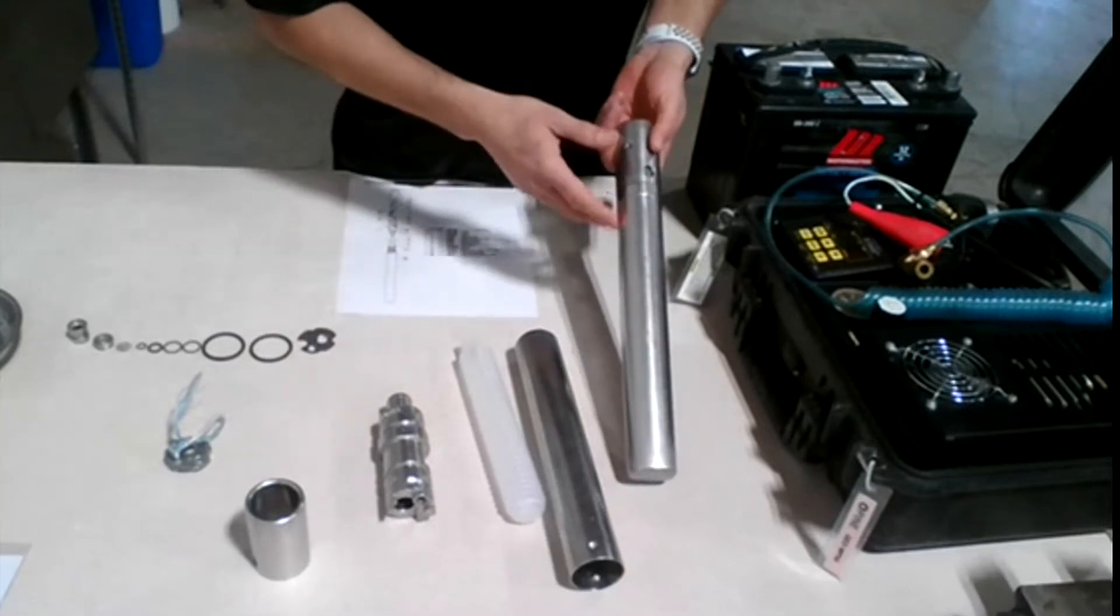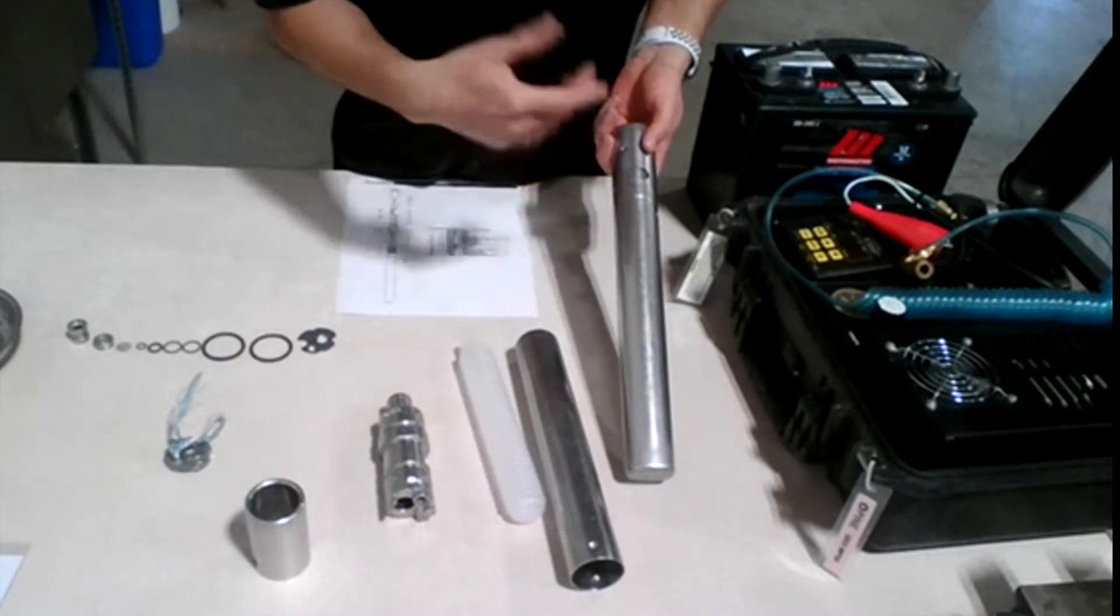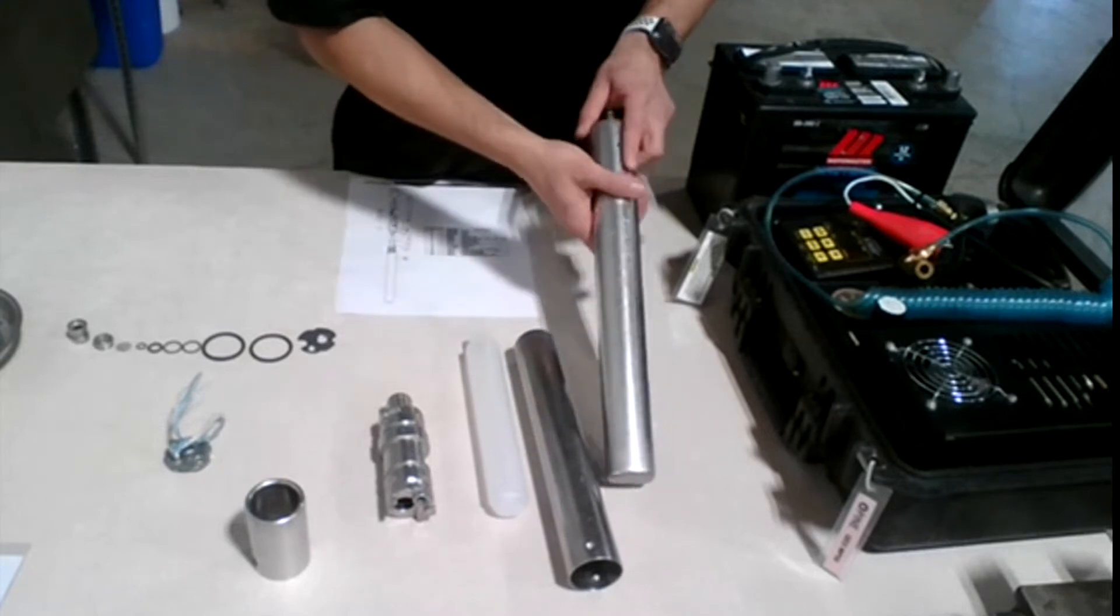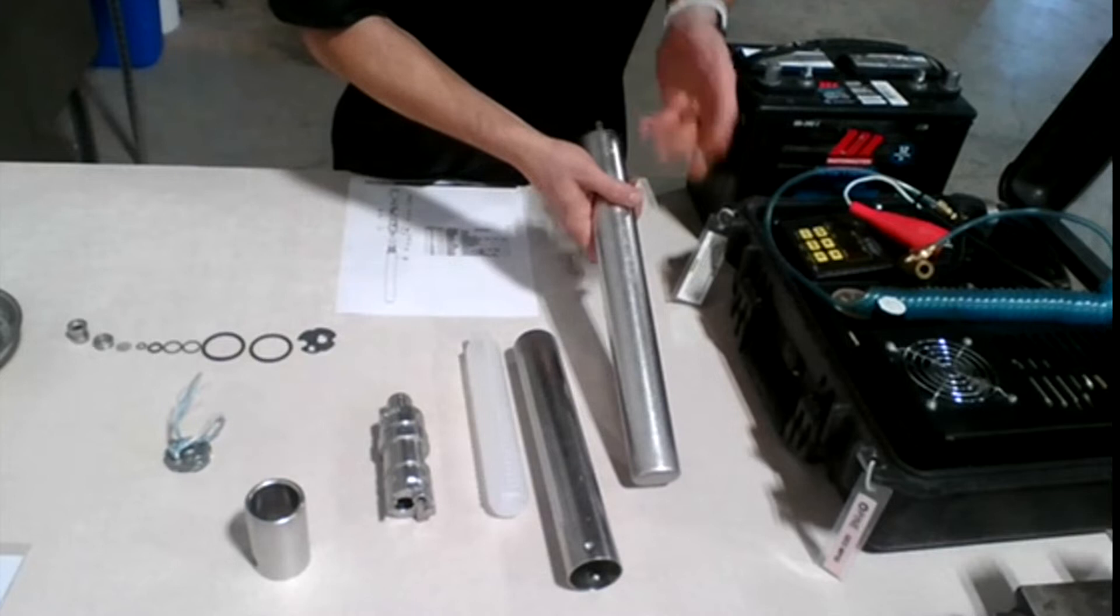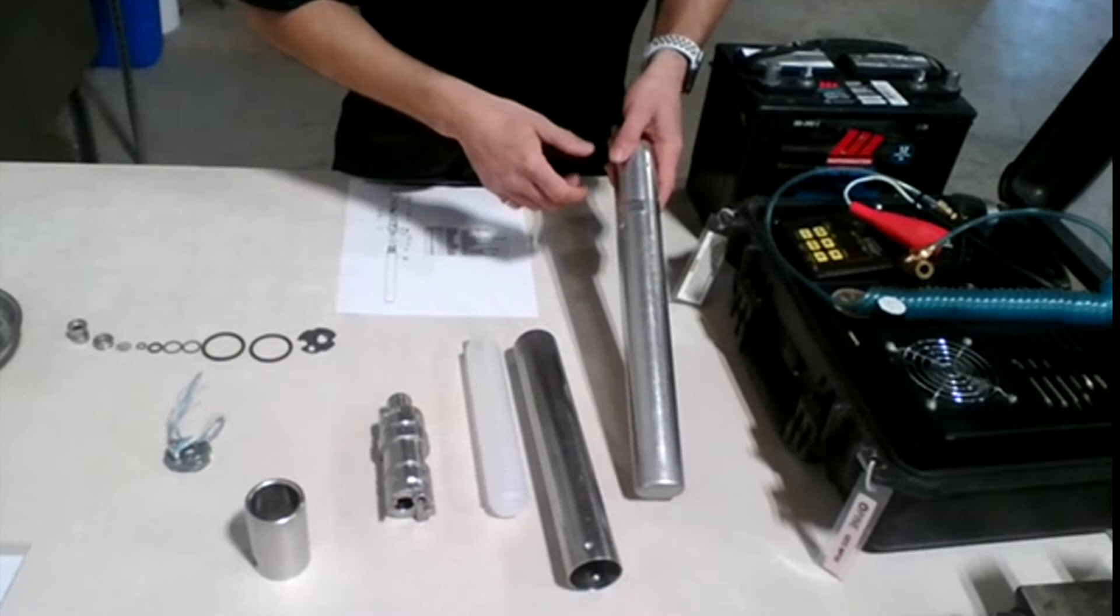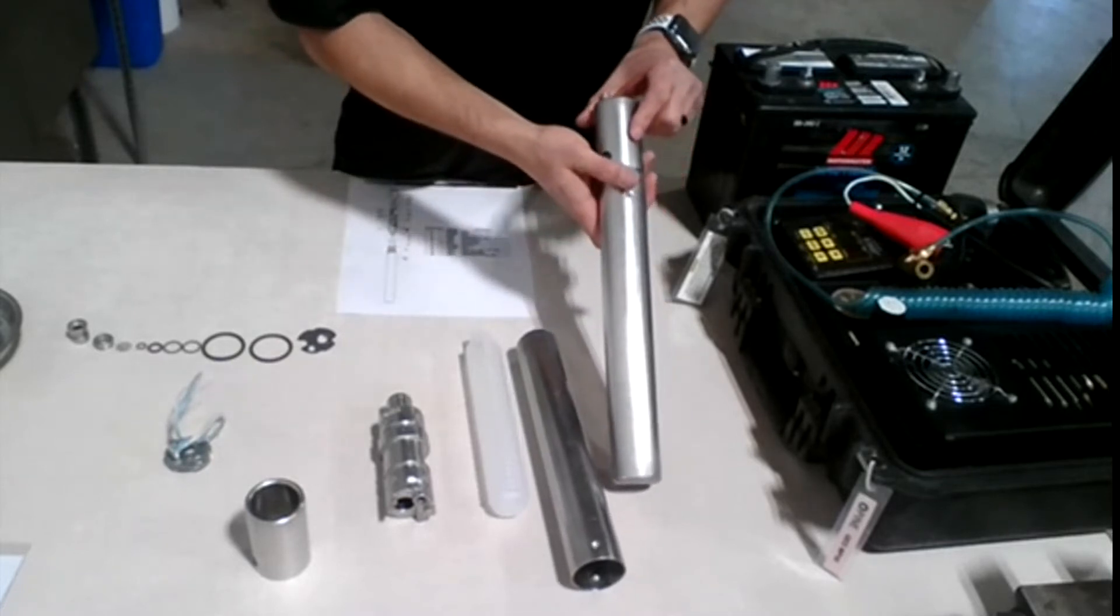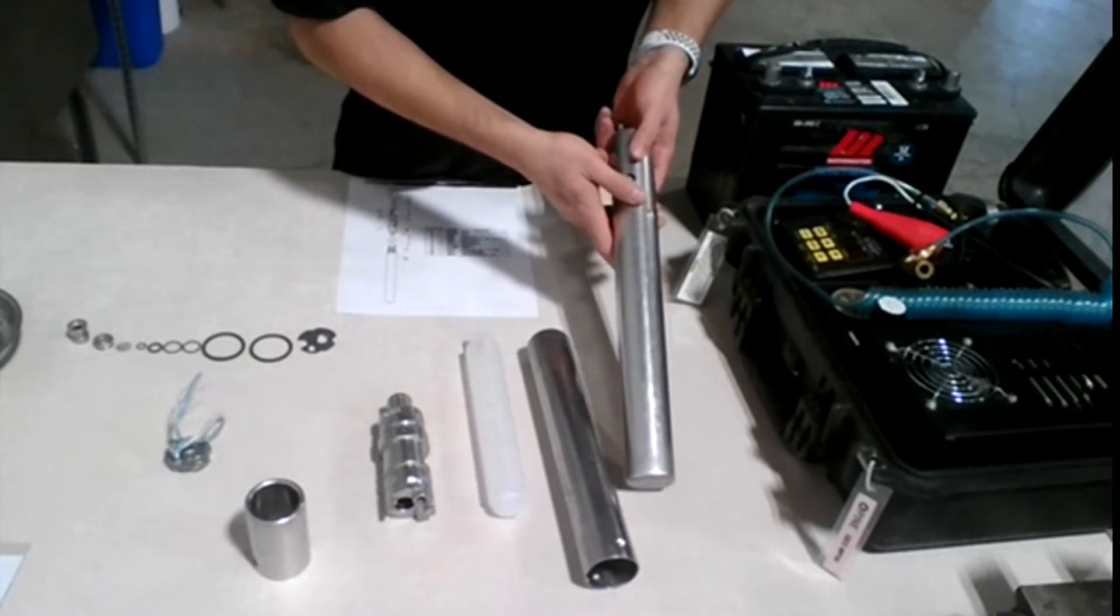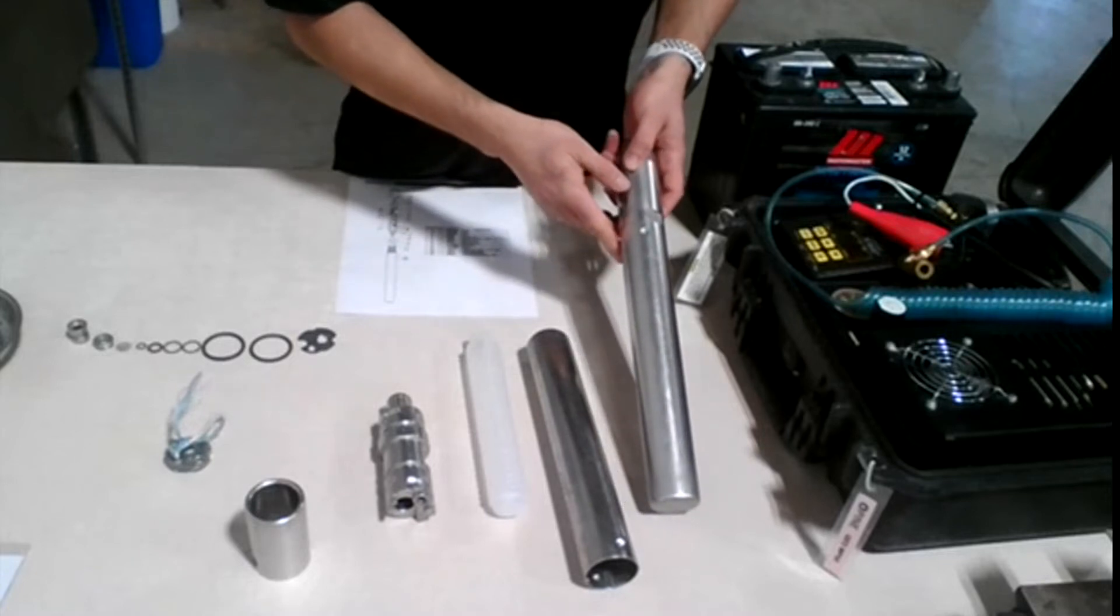So this, it can easily fit inside a bucket. When you are on site, if you want to clean it or disassemble it or swap out the bladders. So this actually, you can clean it on site in a bucket using Alconox, which is really effective detergent and gives you the best results to avoid any cross contamination.